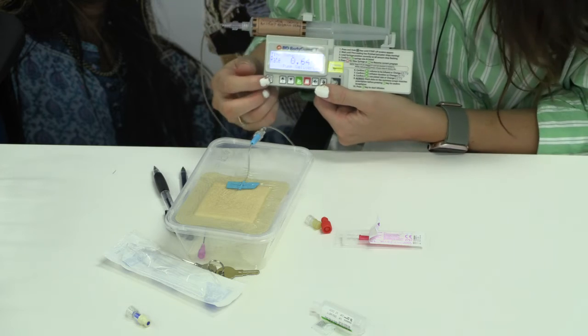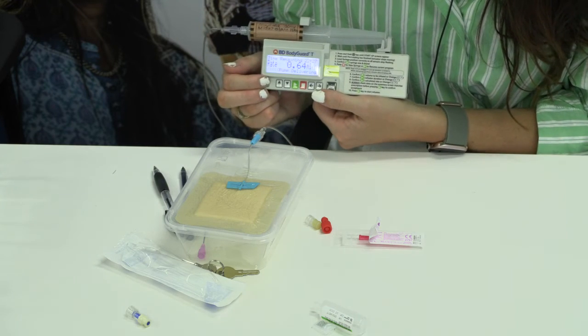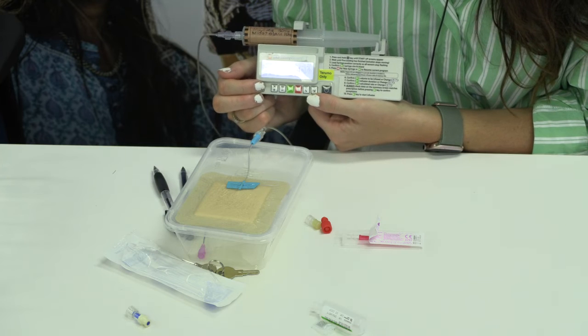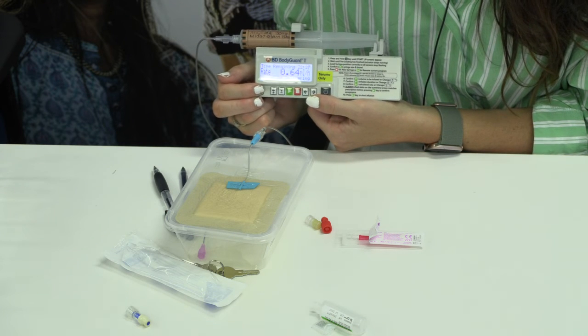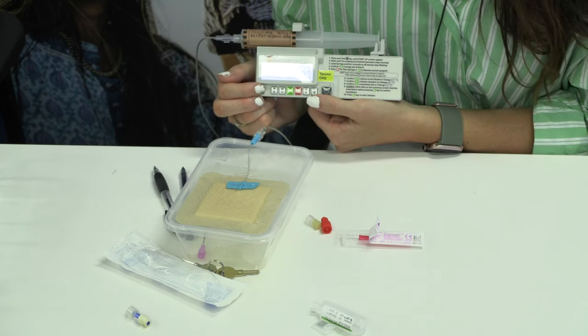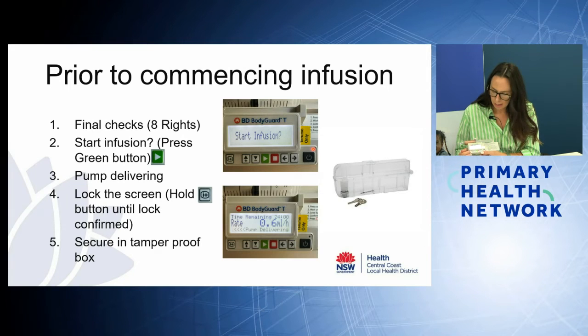Now, obviously, if you need to check the battery status, so at Central Coast Health, we change the battery once they hit below 40%, because we know that we can guarantee that the syringe will last at least 24 hours before that, but under 40% we can't guarantee that the syringe will run the entire 24 hours of its life. So if you've hit below 40% when you change your driver, then change your battery. You'll be able to see that from pressing the I+ button.